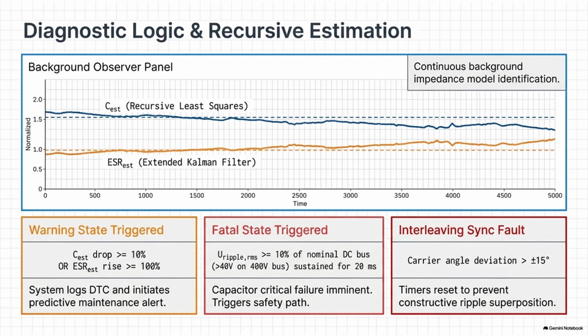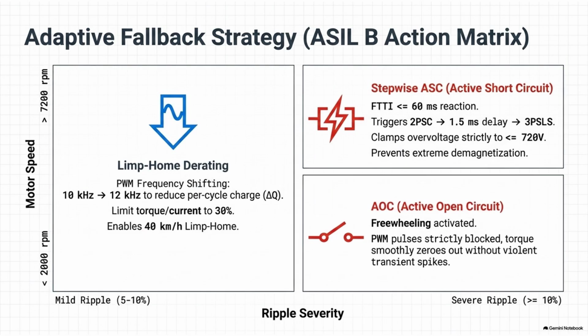The algorithm starts with a mathematical model of what a healthy capacitor should look like. Okay. It predicts what the voltage ripple should be based on the current motor demand. Then it measures the actual voltage ripple. So it looks for the difference. Exactly. It takes the error, the difference between its prediction and reality, and uses that error to recursively update its internal mathematical model of the capacitor's health. So it's continuously refining its understanding of the physical wear and tear of the plastic film, calculating the exact capacitance and resistance dozens of times a second. And the system has absolute thresholds for this, right? Yeah. Like if the algorithm detects that the estimated capacitance has dropped by 10% from its factory rating, or if the internal resistance has jumped by 100%, it flags a level 1 warning. Yes. The system recognizes the component is rapidly aging and it intervenes to slow the decay.